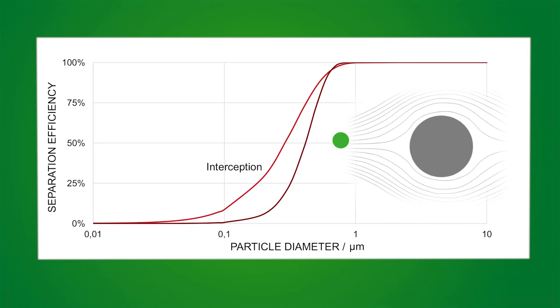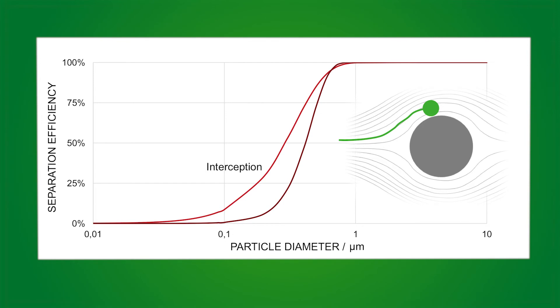The second one is interception. This occurs when particles follow the air streamlines but still hit the fiber because they pass at a distance which is less than the diameter of the particle. This effect is predominant for particles bigger than 0.3 micrometers. The third effect is diffusion. Separation by diffusion happens especially with small particle sizes below 0.3 micrometers — they follow the gross air flow but additionally have an irregular motion pattern called Brownian motion, which increases the chance that the particle hits the fiber.